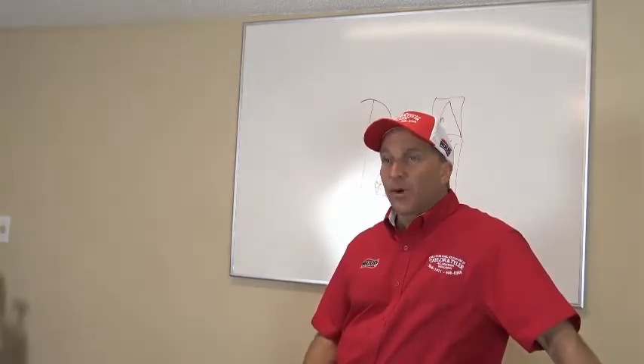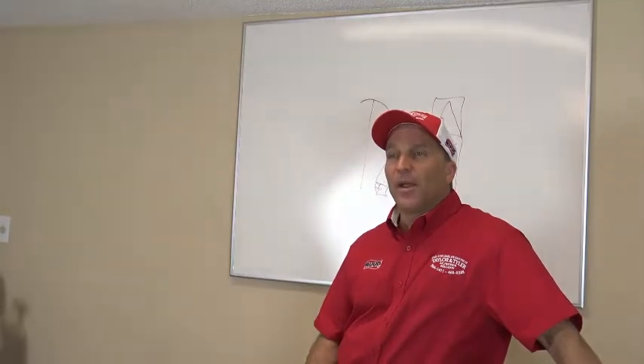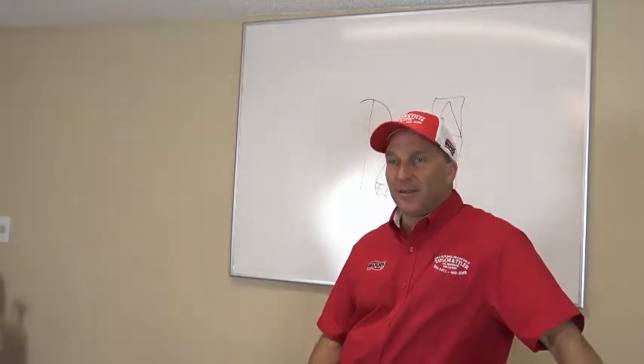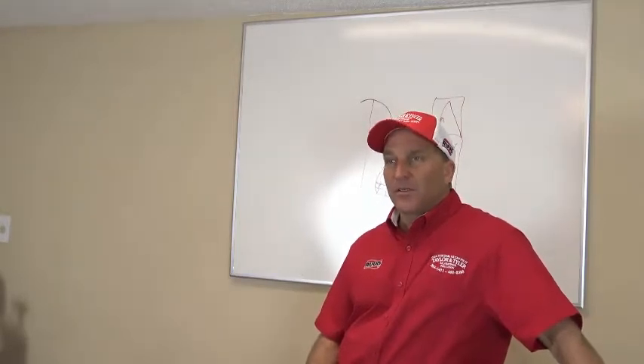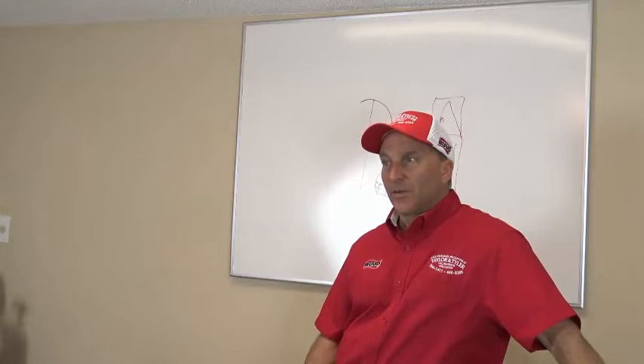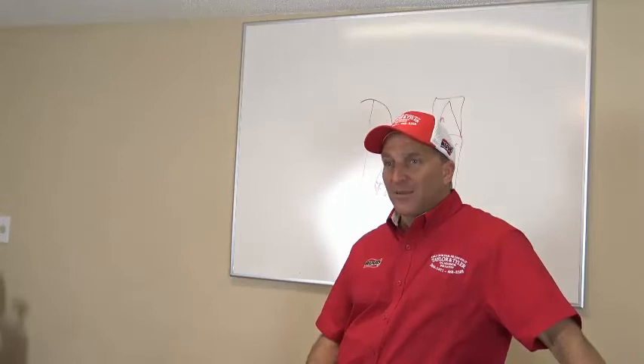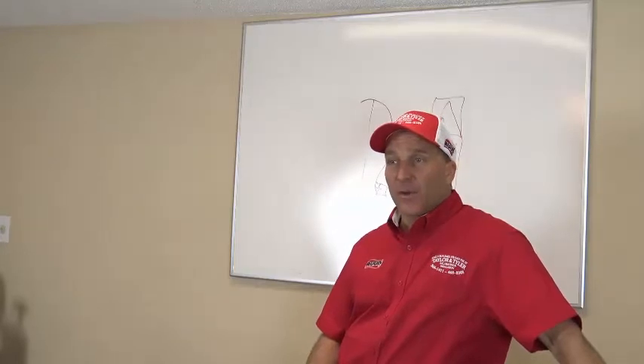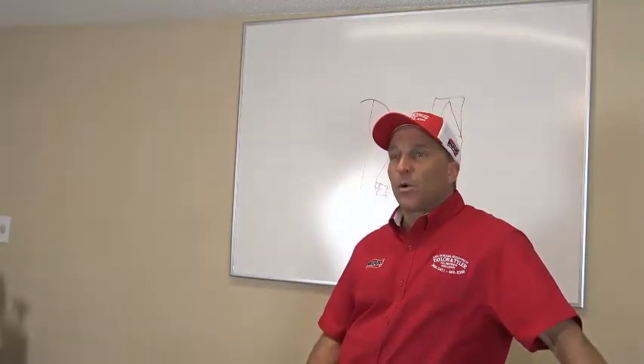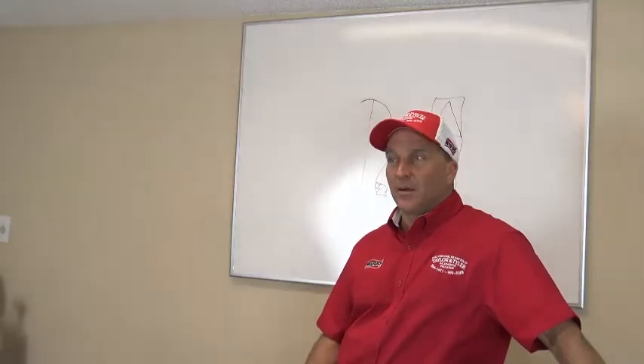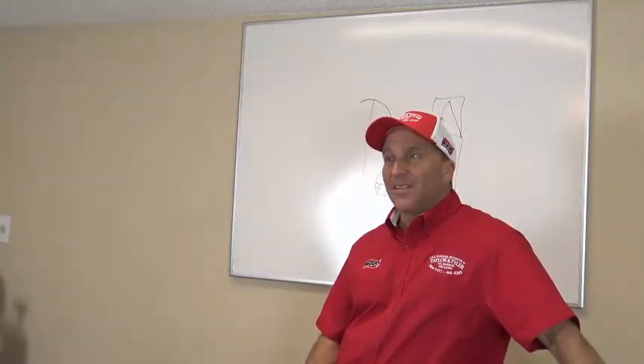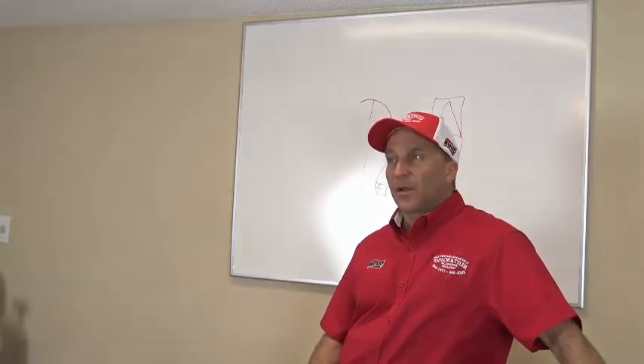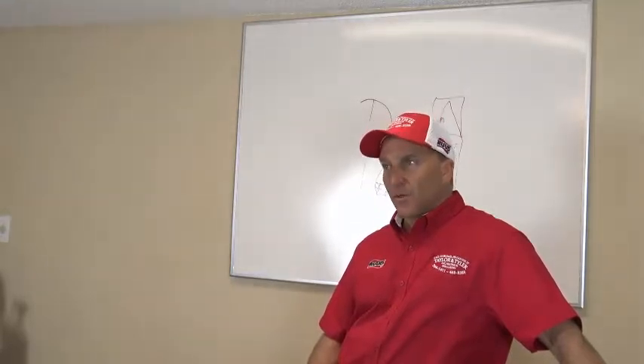If you want me to fix your problem, we need to find your leak and then repair your leak or replace whatever part is leaking. If you'd like me to do a pressure test on the system, you're looking at $550 to do a pressure test on the system. I will isolate your condenser, your line set, and your evaporator coil. We let it sit for a day or two. We come back later and we find out where your pressure is leaking from. If it's in your evaporator coil, I will have to replace your evaporator coil, which will end up costing you about $1,600, $1,800. If you're going to spend $1,600, $1,800 to replace that evaporator coil, I'm going to recommend you replace your condenser as well, because you do have an R22 system and your system is 12 years old.